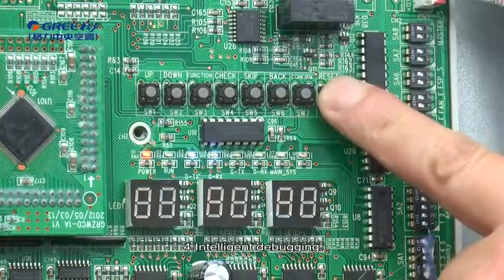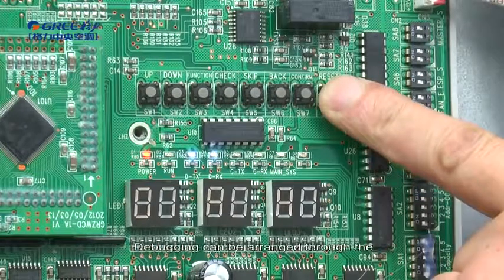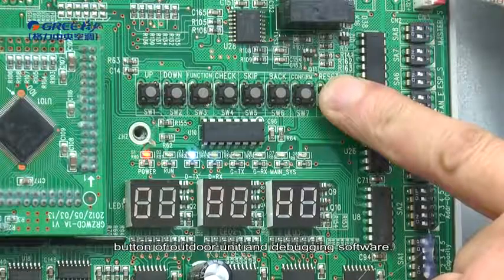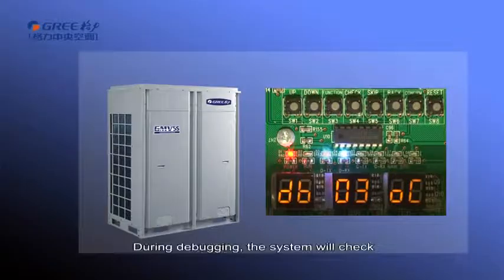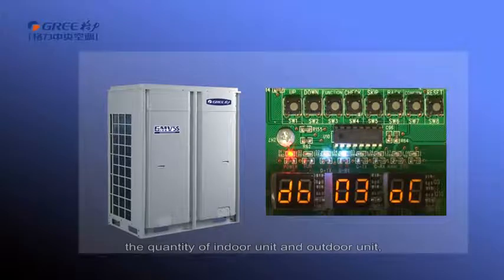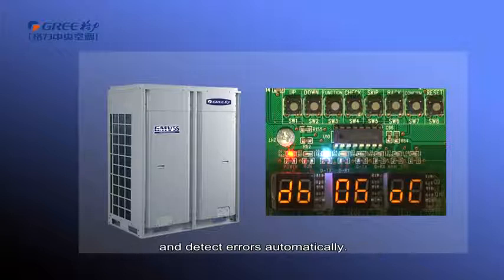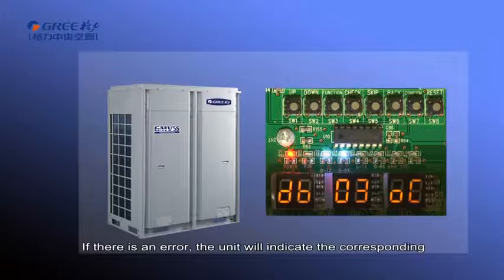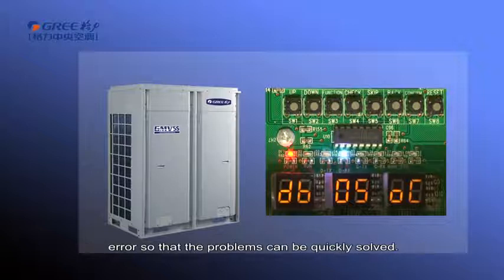The fourth, intelligent debugging. Debugging can be arranged through the button of outdoor unit and debugging software. During debugging, the system will check the quantity of indoor unit and outdoor unit and detect errors automatically. If there is an error, the unit will indicate the corresponding error so that the problems could be quickly solved.